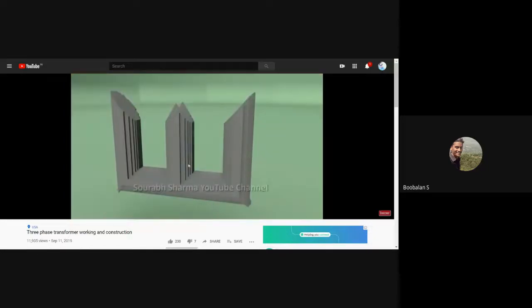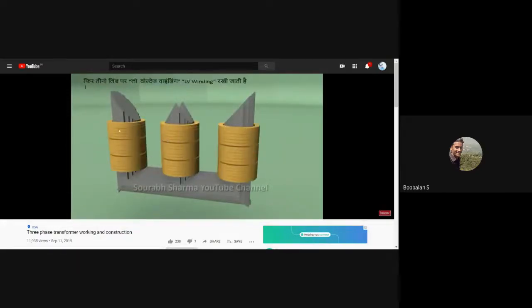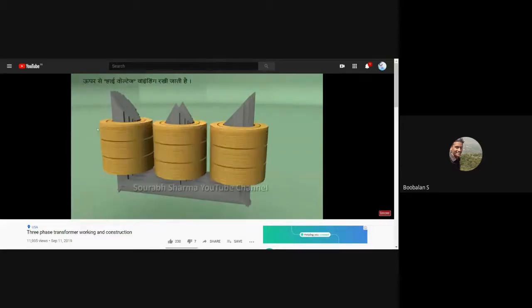In case of a big transformer, paper insulation is used over the limb to electrically insulate the coils or windings from the core. In case of a big transformer, the windings are in the form of discs because it is easy to wind. First of all, the low voltage winding is placed over the limb and over that the high voltage winding is wound. The high voltage winding must be far from the core, that's why first the low voltage winding is wound and then the high voltage winding is wound over that.